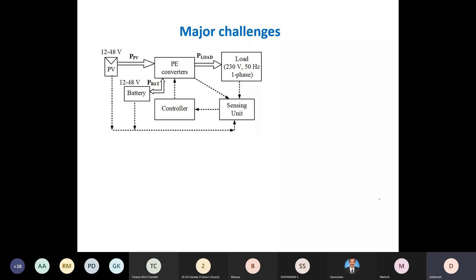Another issue is that if you are designing for high solar photovoltaic voltage, you have to connect several solar panels in series to increase the voltage rating. The maximum commercial voltage available with different manufacturers is generally around 36 volt VMPP for a single module. So you have to connect several of them in series to increase the voltage rating. And as you know, the problem with series connection is that they have to carry the same amount of current, so if one of them is shaded, it will affect the entire string's power output.